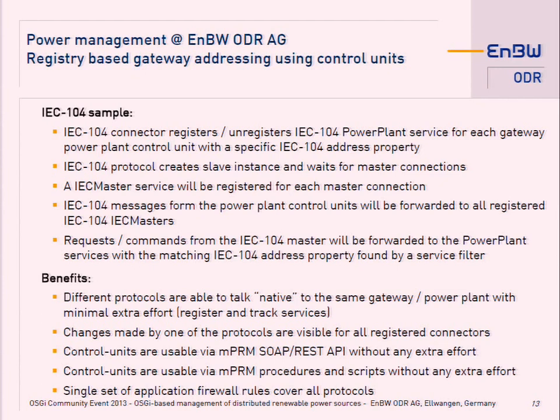The benefit we see from this approach is that different protocols are able to talk natively in the same way to a gateway, power plant, with minimal extra effort. You just have to register in the registry. And it's also transparent for all different protocols. If you talk Modbus to the gateways, or if you talk IEC 104, every protocol sees the changes transparently.